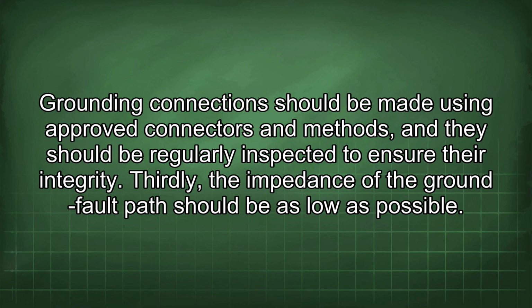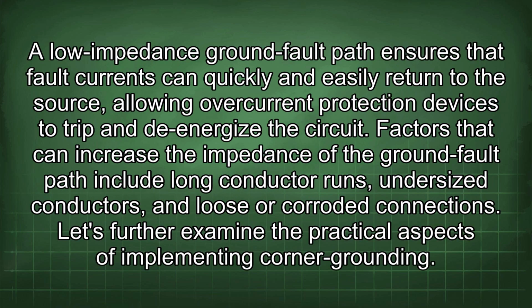Thirdly, the impedance of the ground fault path should be as low as possible. A low impedance ground fault path ensures that fault currents can quickly and easily return to the source, allowing overcurrent protection devices to trip and de-energize the circuit. Factors that can increase the impedance of the ground fault path include long conductor runs, undersized conductors, and loose or corroded connections. Let's further examine the practical aspects of implementing corner grounding.